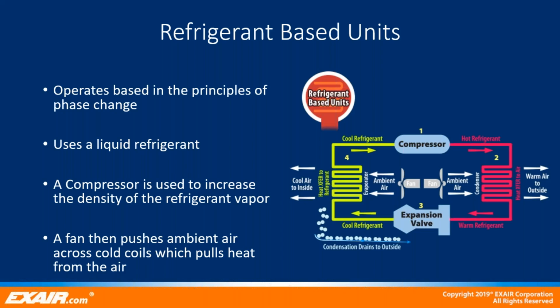This hot, high-pressure vapor then travels to the condenser, where it moves through a series of coils with thin fins attached. A fan blows over the fins, and heat moves from the refrigerant to the fins into the airstream, and then is vented outside of the system. Now that the vapor has lost a significant amount of heat, it changes phase from a gas to a high-temperature liquid.